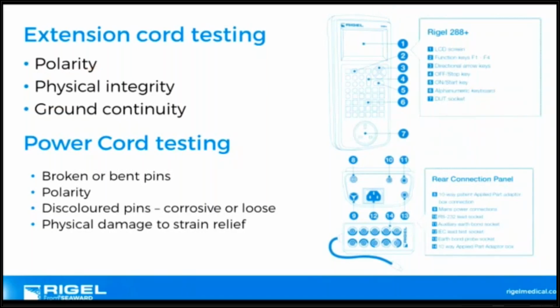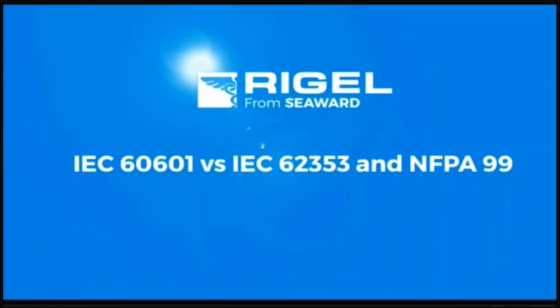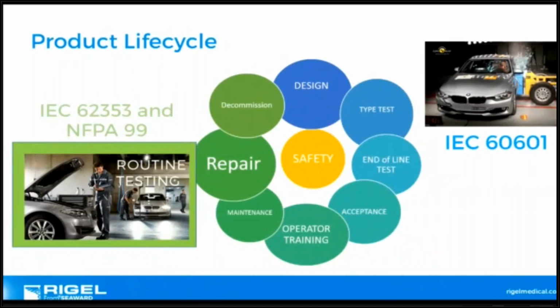So that's a feature that people aren't aware of with the 288, which I thought I would put in here. So what's the difference? I've got to stress 60601: design, type test, end of line, crash test dummy. If I'm a medical device manufacturer going to bring out a device to the market, I must make sure I've dotted my I's and crossed my T's before it's released, to make sure it's free of this electrical hazardous leakage current.